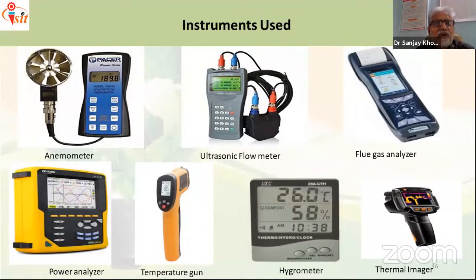This is basically required for ventilation, HVAC applications, ducting, wherever there is duct and air is flowing. Here we can use the anemometer, and this instrument is very much essential. Even if you go to the boiler, ID and FD fans are there, so how much air is entering through the ID and the FD. So everywhere you need this anemometer. All these instruments are compatible with the computer. It has its own memory, and if you connect it to the computer, you will get the data in Excel.